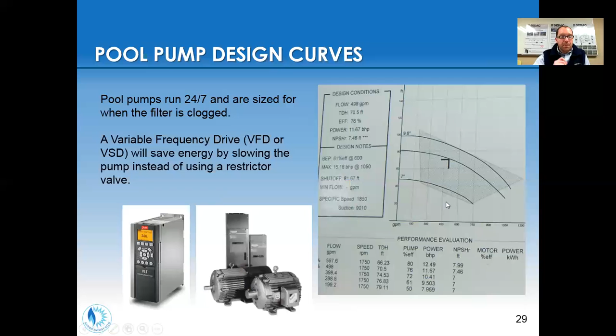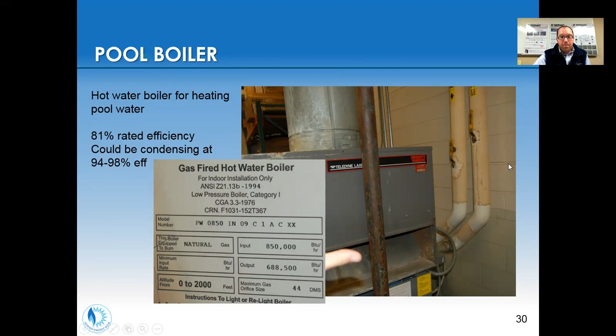Pool boilers, looking at what pool boilers exist. In this case, this was rated at 81% efficiency. It's pretty old, so it's possible that it's lost some of its efficiency as well. But this could be upgraded to a condensing boiler at 94 to 98% efficient. You can find the efficiency of your boiler by looking at the input and the output, and dividing the two to find out what the efficiency of the boiler is. And that means in this case that almost 20% of the heat is just going up the flue stack and being wasted.